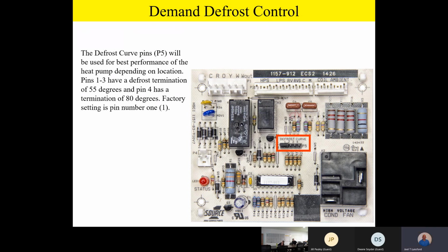That is a really, really good question. All right, so what they call a defrost curve. Even though the temperature termination point is going to be 55 degrees on pin number 1 through 3, how that thing defrosts, and specifically what it looks at as far as outdoor ambient temperature, there's a pre-programmed algorithm in there that's a little bit different between the tonnages.